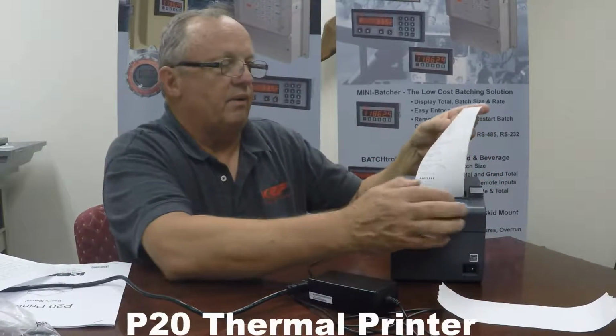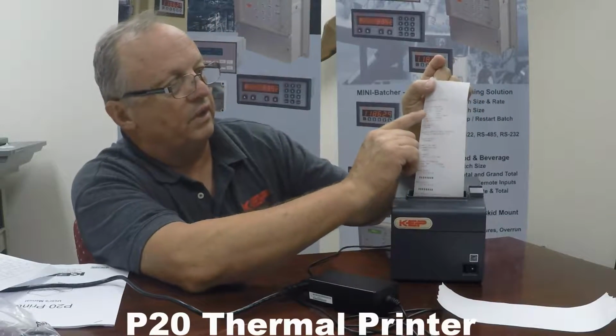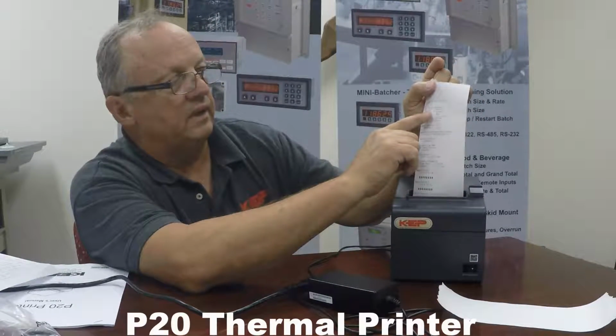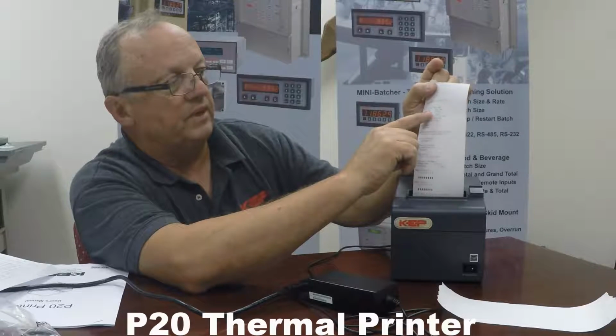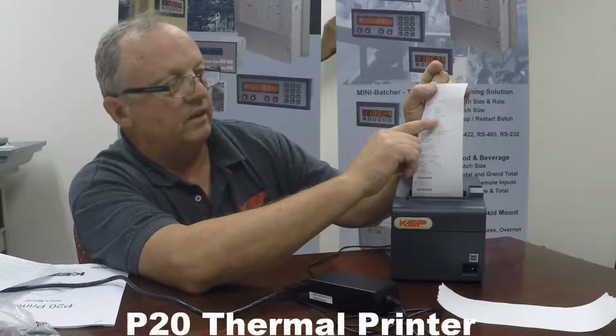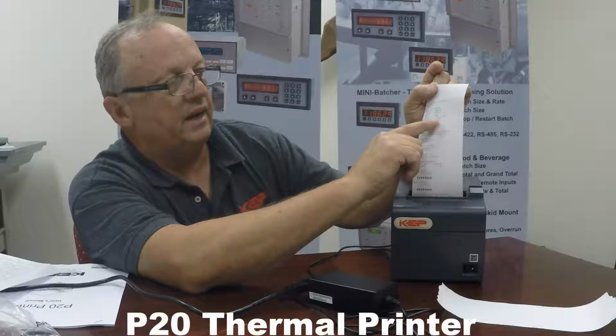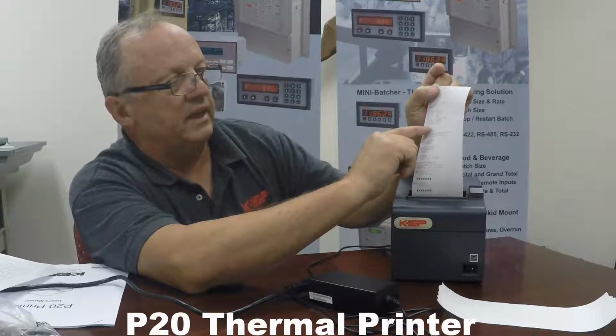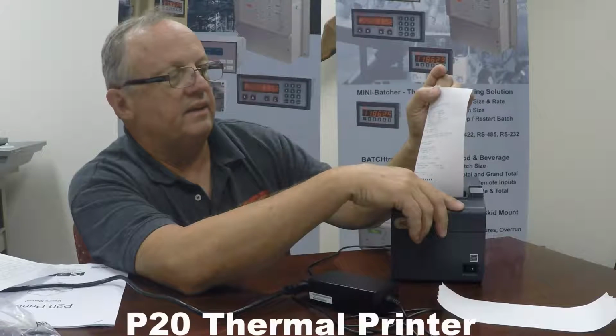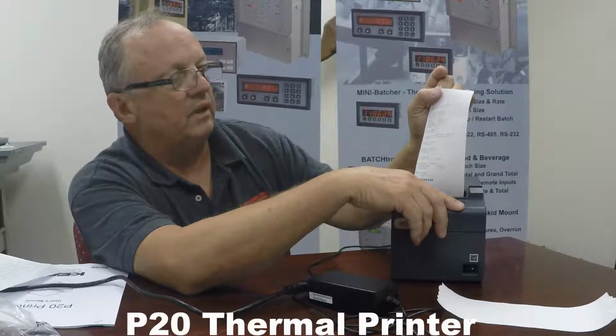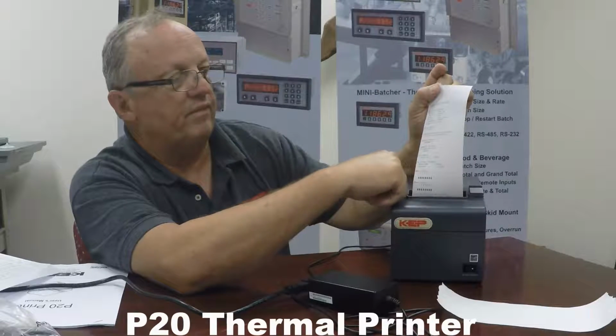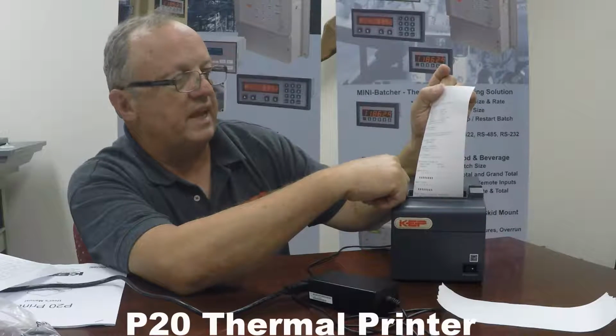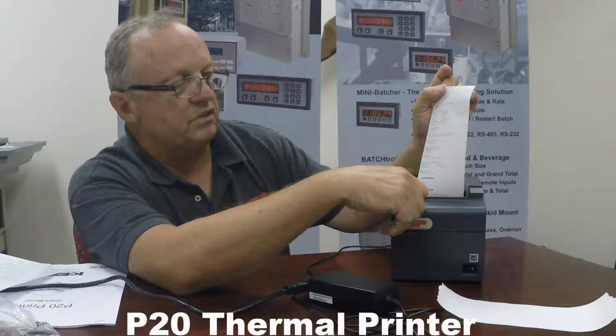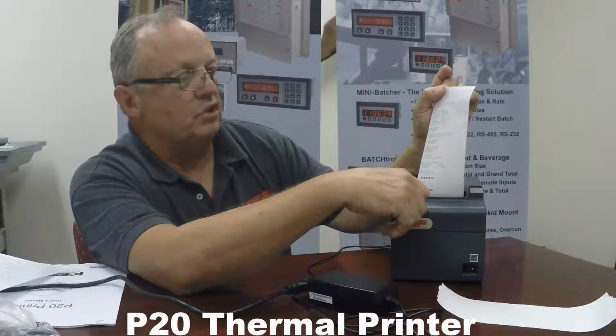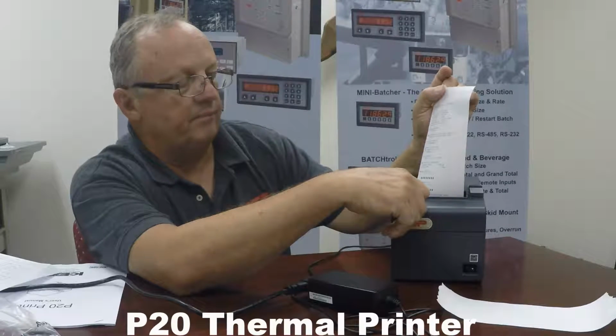What's been created right now is a listing showing you the settings for the instrument that would also match in the printer. In this case, 9600, 8 data bits, no parity, 1 or more stop bits, handshaking by hardware control lines, and what to do in the event that it receives a questionable character. There's also selections for the size of the buffer and other settings for it. Not all of these are supported by the Supertrol, so we're going to be using a more basic set.